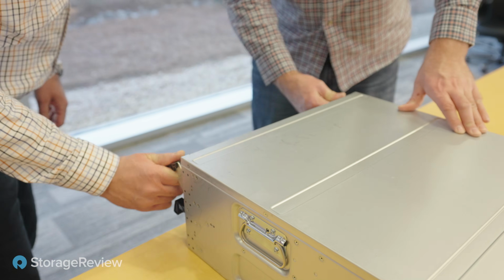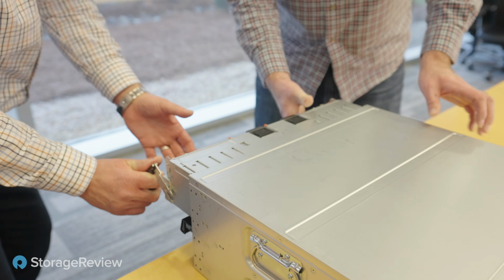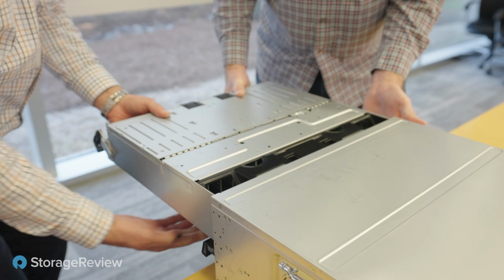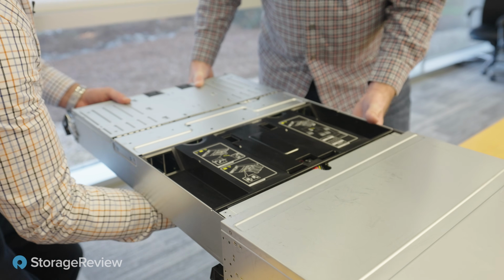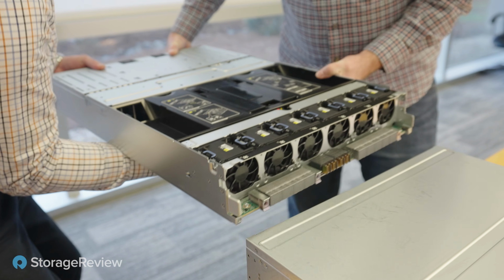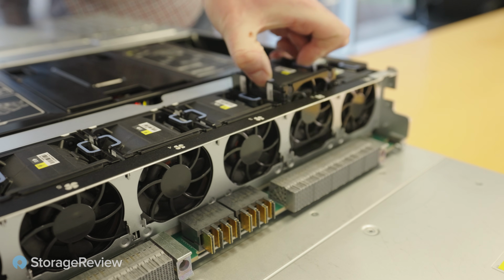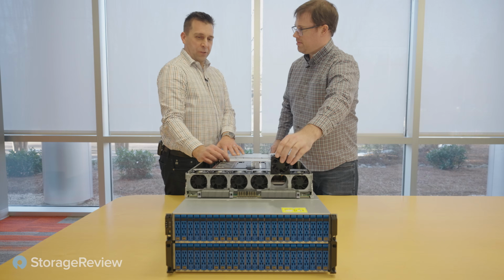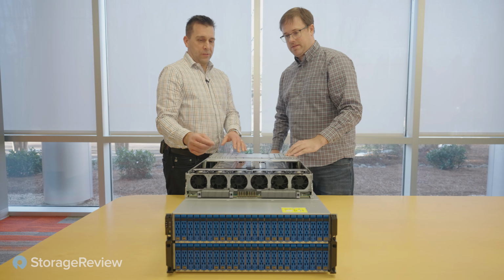Well, that sounds great. And from the serviceability side, let's start taking this thing apart so we can look at the internal components. Absolutely. So what you do is you grab hold of these two black handles here, pull down, and the whole unit disengages from the chassis. As you can see up here in the front, we have a collection of 6 hot swappable fans. So in case one of these fails, you just grab, squeeze, lift it out. Yep. Get your replacement, drop it back in. Pretty easy to take apart.